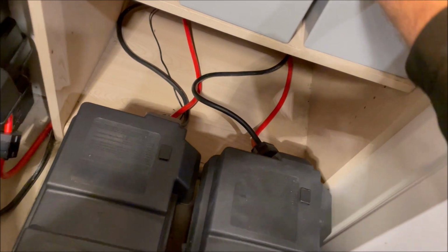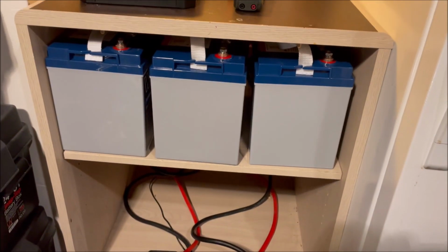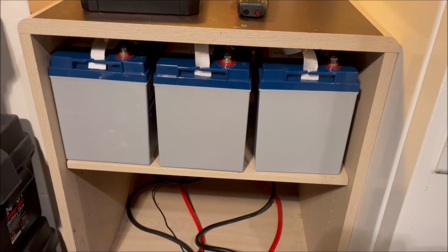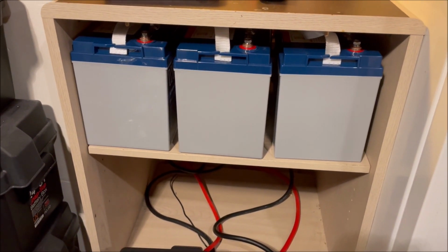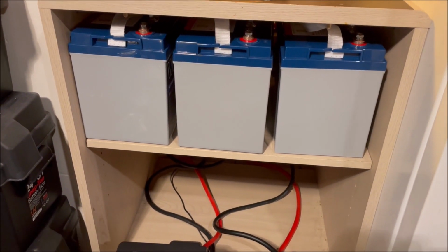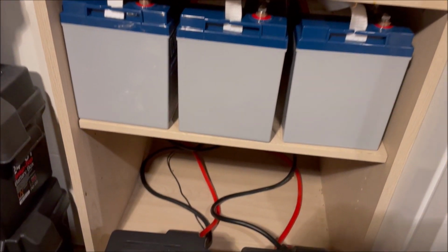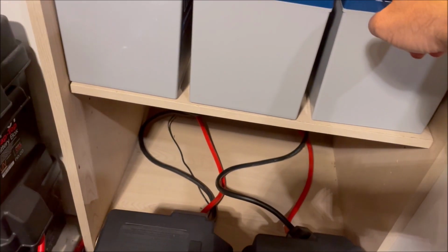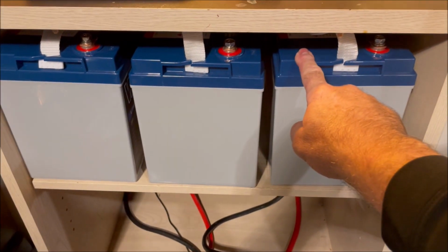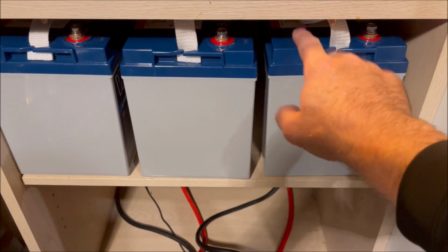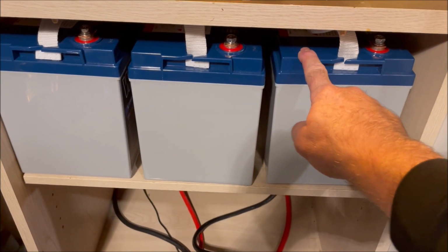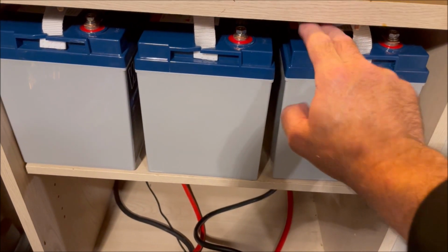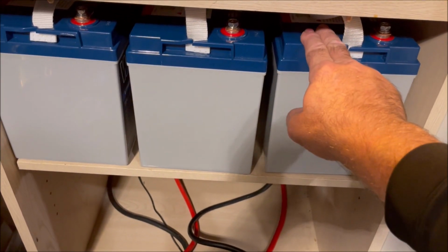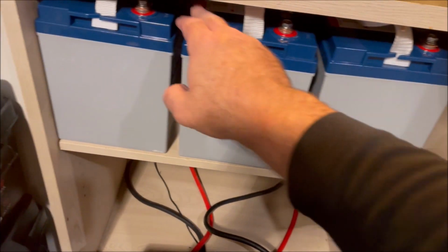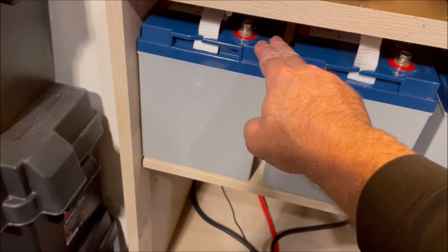So basically we've got these two outer batteries are a little bit out of balance with the rest of them. So as the system is charging up, the BMS probably in this one, because it was the last to come back on, one cell gets too high. One cell gets above 3.65 volts, and it does a cell over voltage, and the BMS cuts it off. And then this one comes in shortly after that.